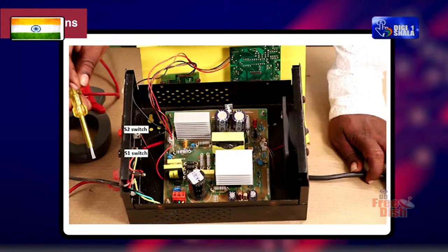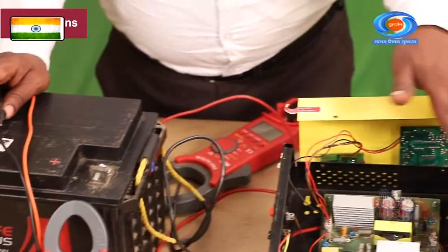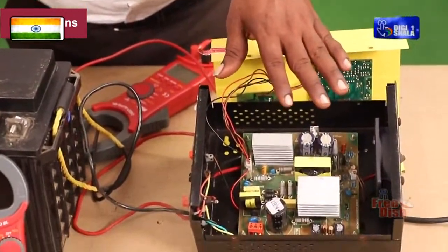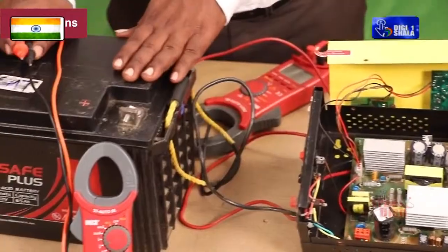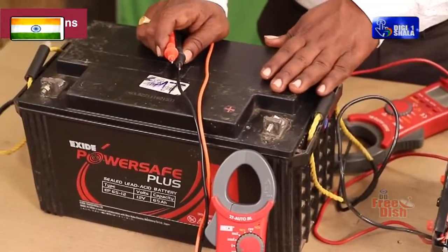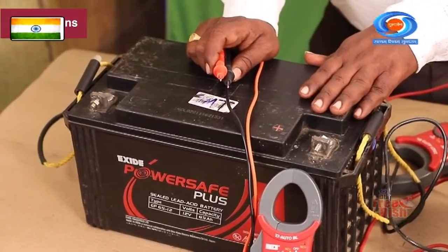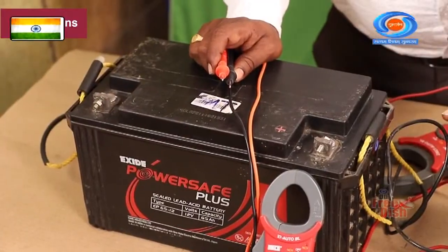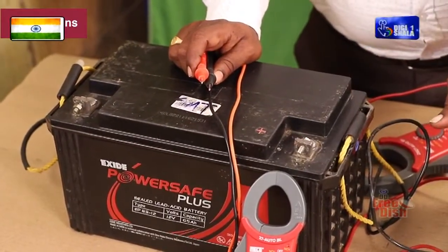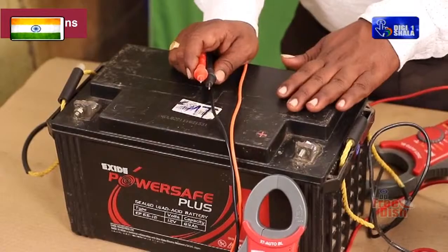Set the auto transformer X2 in 0 level position before charging the battery. Keep the switches S1, S2 and S5 in an open position. Connect the battery to the charger output terminal, positive terminal to the battery positive pole and negative terminal to the battery negative pole, and close the switch S3. Check the readings in the voltmeter, which is connected through diode D9 and switch S3.